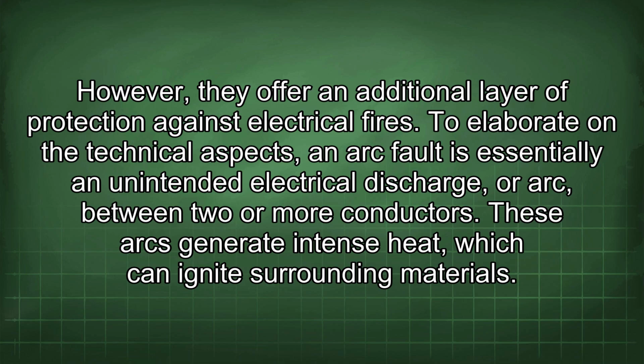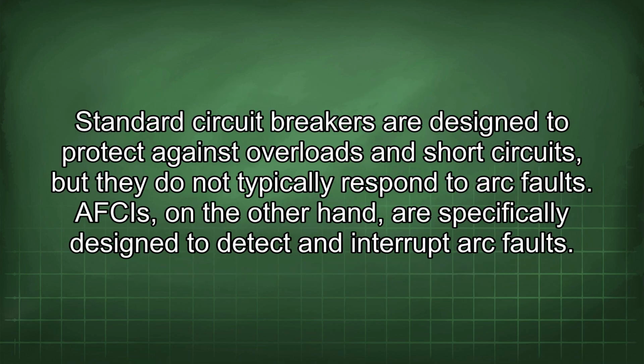To elaborate on the technical aspects, an arc fault is essentially an unintended electrical discharge, or arc, between two or more conductors. These arcs generate intense heat, which can ignite surrounding materials. Standard circuit breakers are designed to protect against overloads and short circuits, but they do not typically respond to arc faults. AFCIs, on the other hand, are specifically designed to detect and interrupt arc faults.